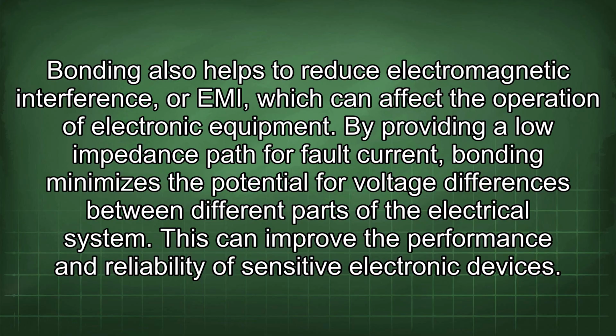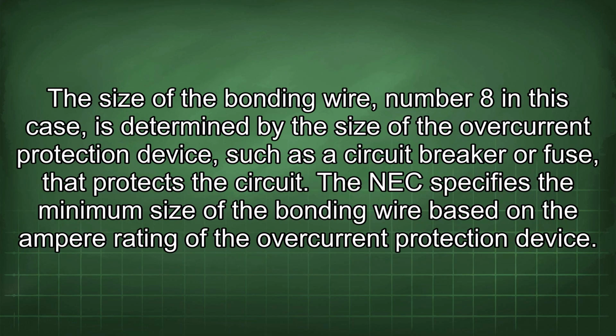This can improve the performance and reliability of sensitive electronic devices. The size of the bonding wire, number 8 in this case, is determined by the size of the overcurrent protection device, such as a circuit breaker or fuse, that protects the circuit. The NEC specifies the minimum size of the bonding wire based on the ampere rating of the overcurrent protection device.